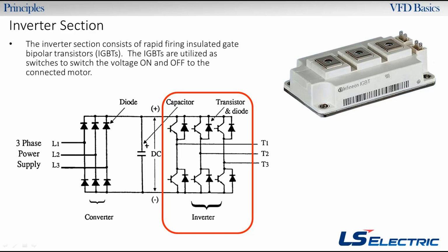So this is kind of what an IGBT is going to look like. It looks very similar to the diode, right? But there are these terminals on the right side here. These are actually your gates. So these need to be fired whenever the drive tells it to fire. When I say firing, it means switching it on and off. So that all goes back to the processor and all that stuff. Whereas with diodes, there's no firing. They'll automatically let the current through or they won't.